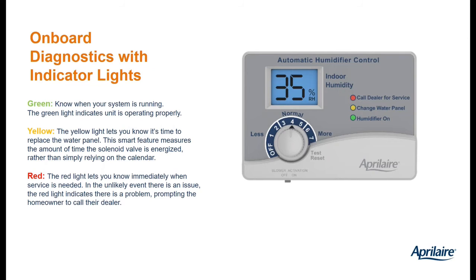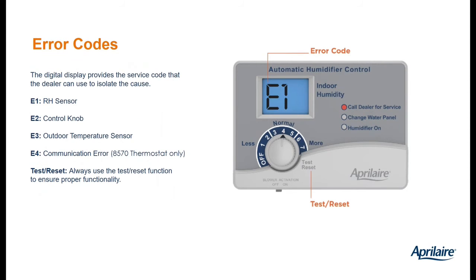Another advantage of the automatic humidistat, besides the automatic humidity adjustment and the blower activation option, is that you have diagnostic LEDs, or status LEDs, let's call them. You can see there's 3 LEDs. Green at the bottom tells you when the humidifier is on. Yellow in the middle tells you change water panel. And then red at the top tells you if there's a problem. You see call dealer for service. And when the red LED for call dealer for service lights up, the display changes to an error code. So it's obvious that there's something going on. You can see an E1, an E2, an E3, or an E4.